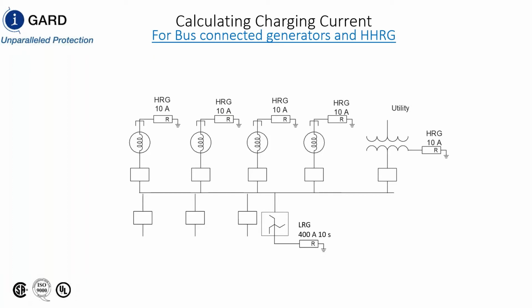then yes, you want to protect your generator. And the typical fault that you're going to have on the generator, and what you need to protect it against, is a medium voltage stator winding fault. So you want to minimize the damage should you have a stator winding fault. So it's in your best interest to put in a hybrid high resistance grounded system.